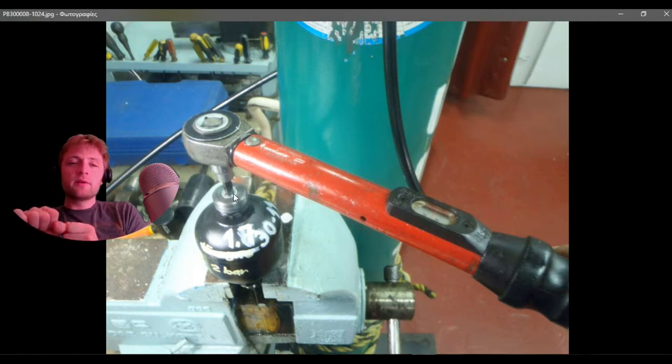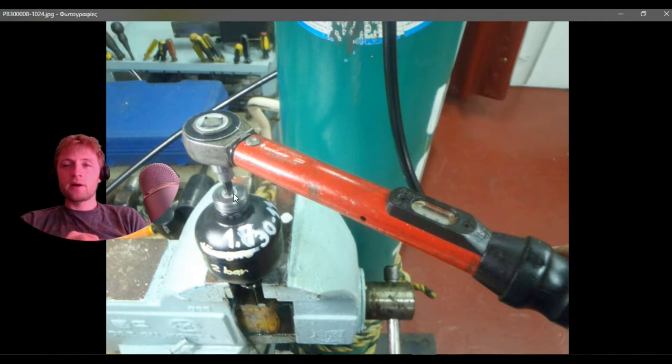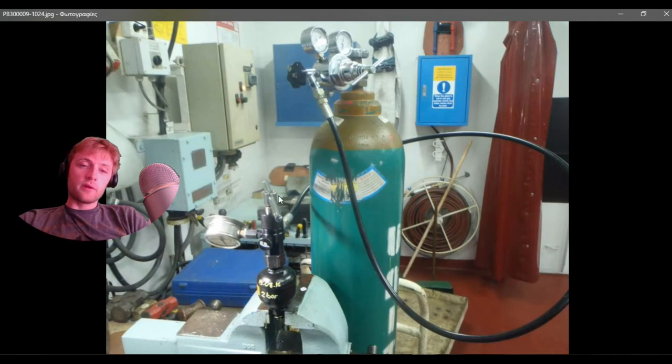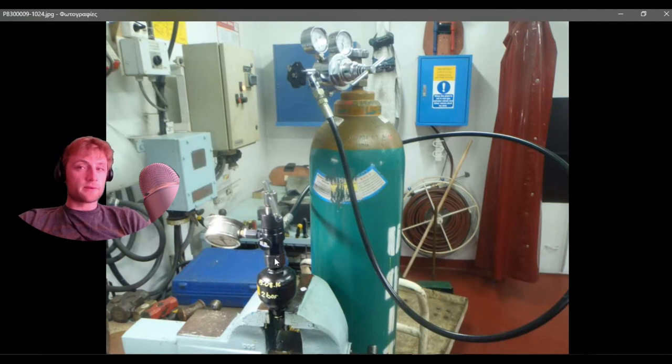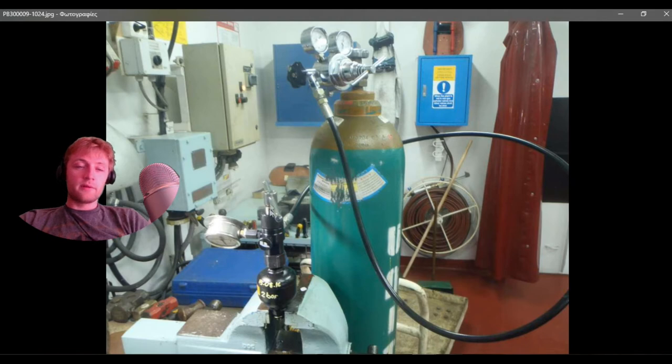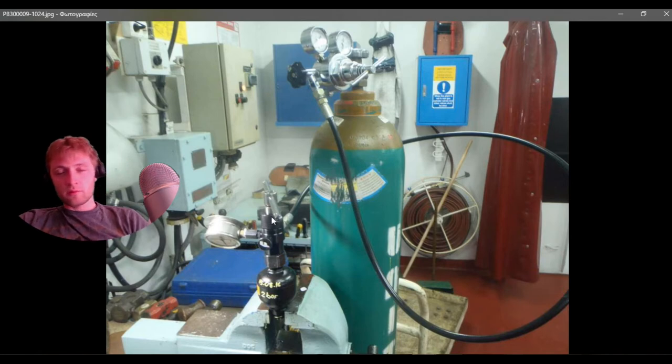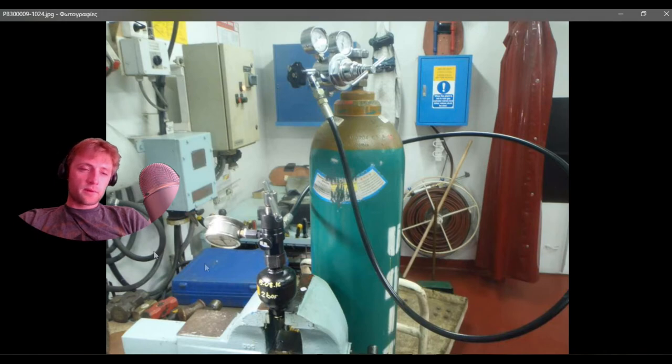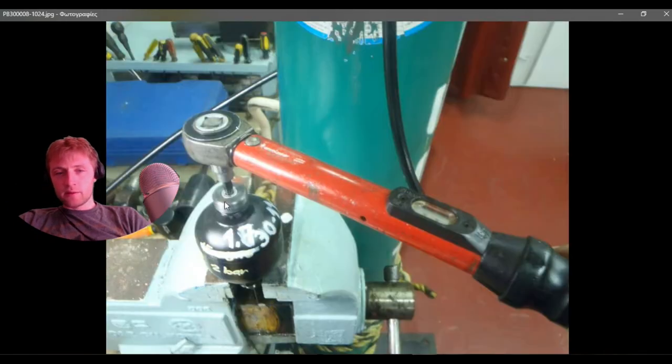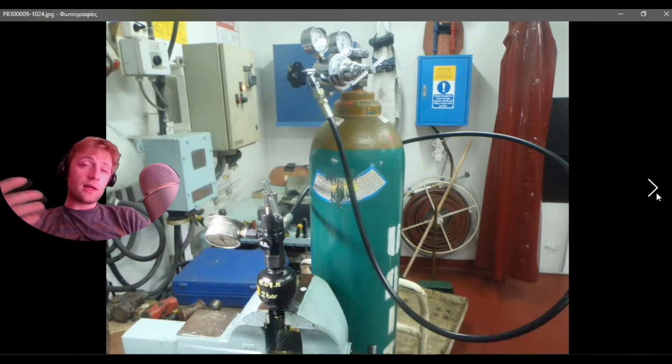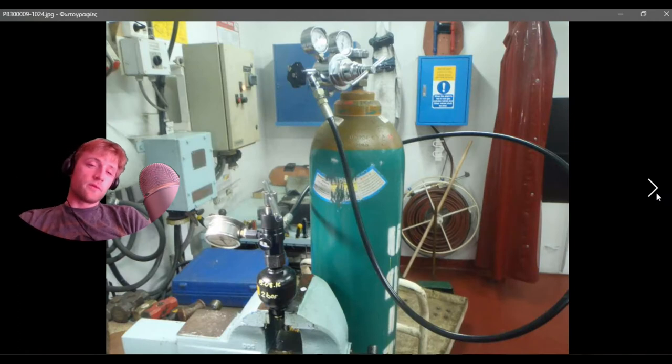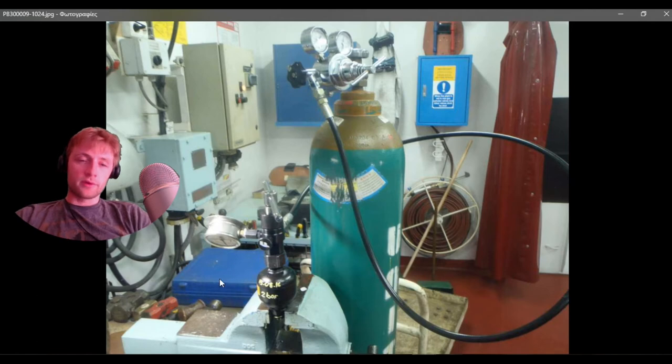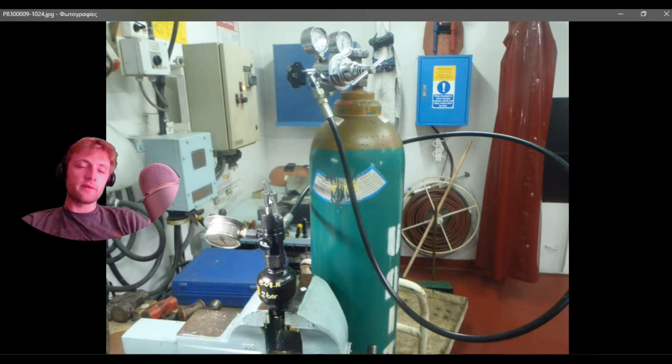What you do before you fill: you take an allen key and release it just a little bit, because this is really hard tightened. If you use this tool here, for sure you will break the allen that is located inside, and then you cannot operate this equipment. This equipment here with this handle is like a valve to close and open the allen key, which allows the nitrogen to enter inside the accumulator.